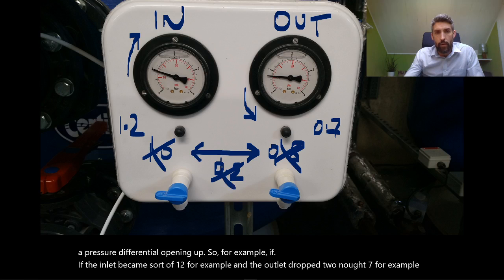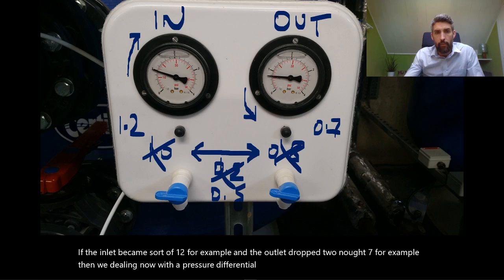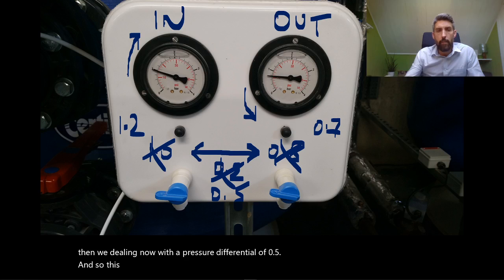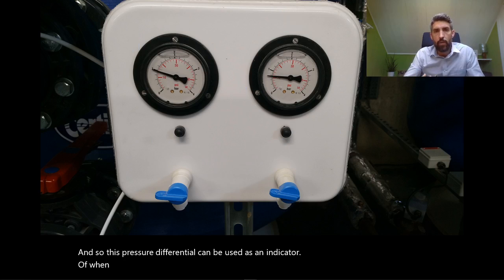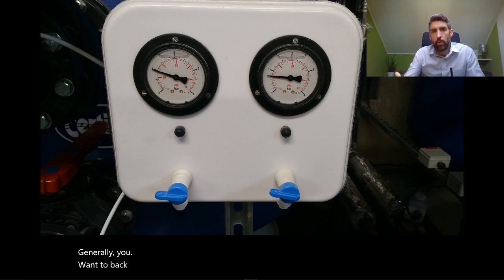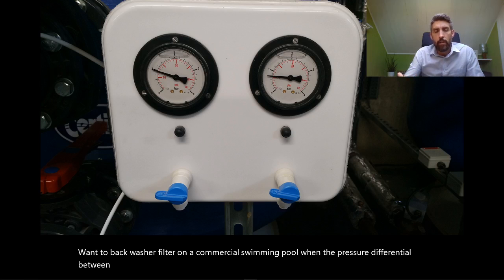This pressure differential can be used as an indicator of when the filter needs to be backwashed. Generally you want to backwash a filter on a commercial swimming pool when the pressure differential between the inlet and the outlet reaches something in the region of 0.4 or 0.5.